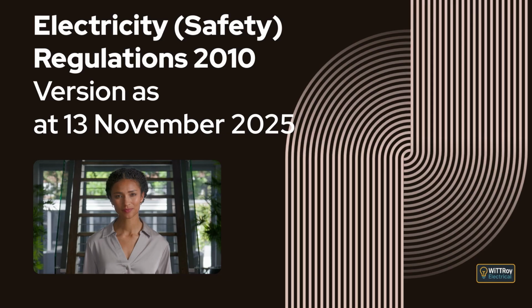It explains that the appliance must be confirmed as electrically safe in accordance with ECP 50 for domestic appliance maintenance work, AS/NZS 3551 for low or extra low voltage electrical medical devices, or AS/NZS 3760 for all other low or extra low voltage appliances. It also explains that if an appliance is electrically unsafe, it must be adequately disabled and marked, and that doing so in accordance with AS/NZS 4701 is treated as compliance.